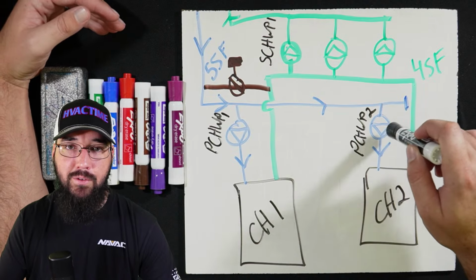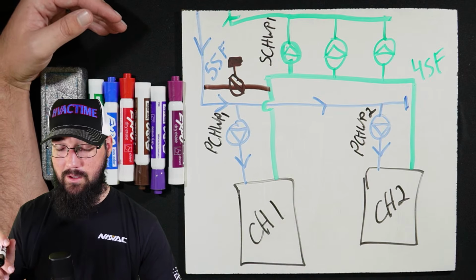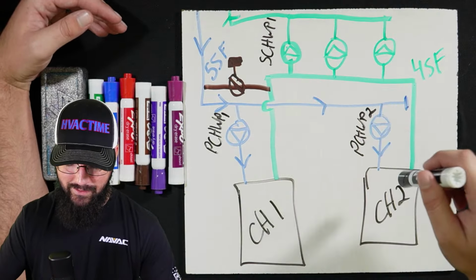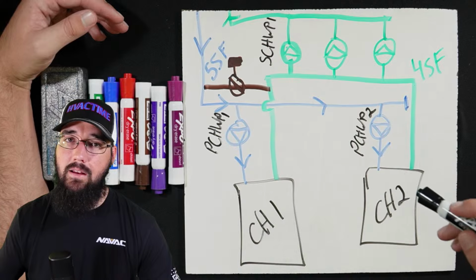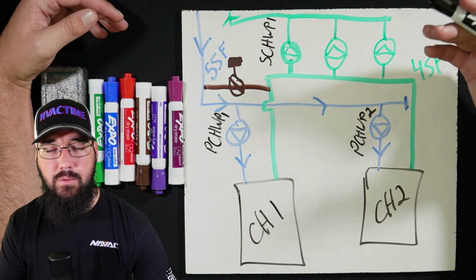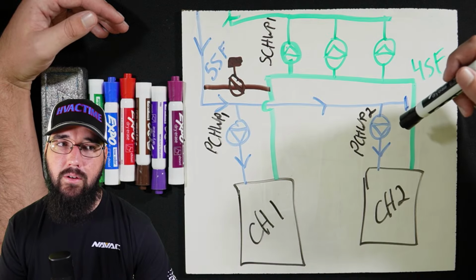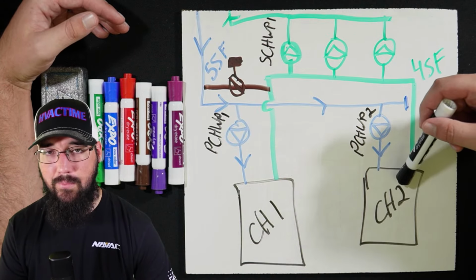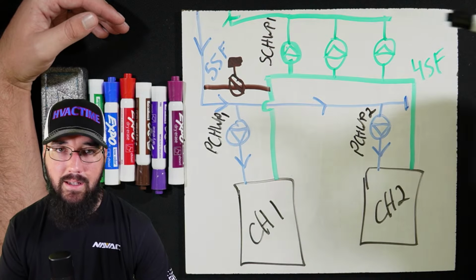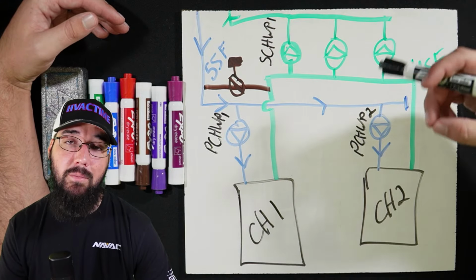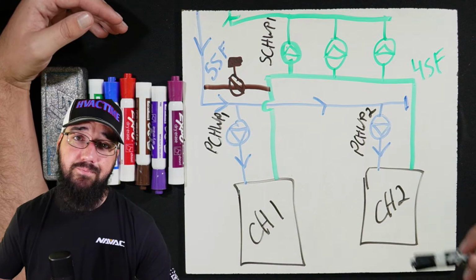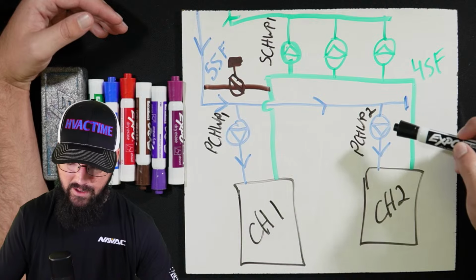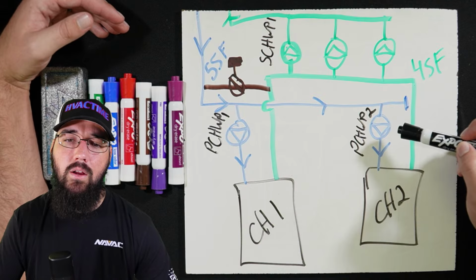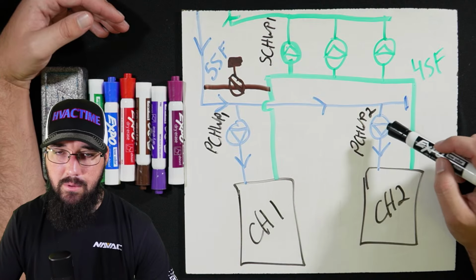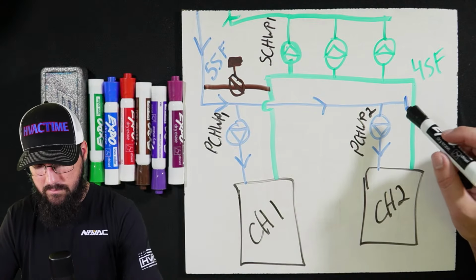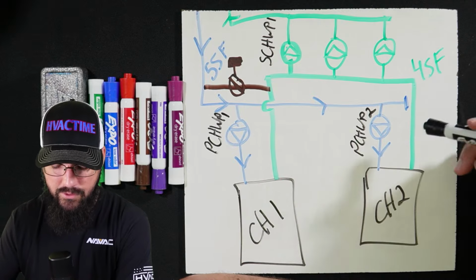These primary pumps, their main focus is not the main loop flow. It is the chiller's flow. And they will be calibrated, whether they're variable speed, however they're configured, they'll be set to at least the minimums of the chiller. At least. When I say minimums, I mean GPM. So we're taking a DP here. We're getting our GPM through the chiller, and then we're going to use that to configure how the drive or the starter, whatever the case may be, for the pump to work and function.